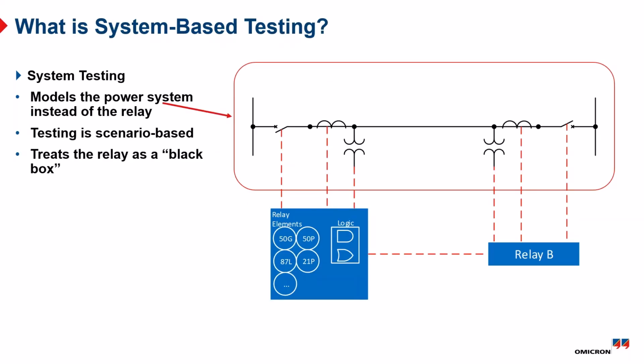The alternative to function-based testing is something called system-based testing. And system-based testing is, instead of modeling the relay, we model the power system. So here we create a single line diagram of the power system, and the software uses full simulation to develop the voltage and current signals. Now we create faults on our diagram. The software then calculates the proper realistic inputs, and we verify the relay's response that way. So in this case, we treat the relay like a black box, and we simulate the different system conditions to that black box and make sure that the box has the proper output.